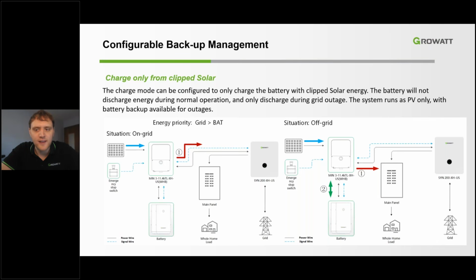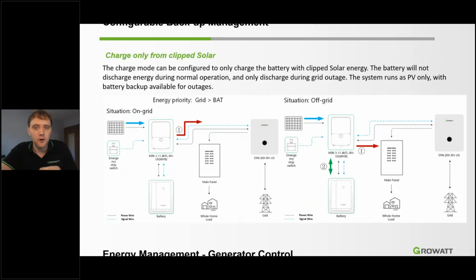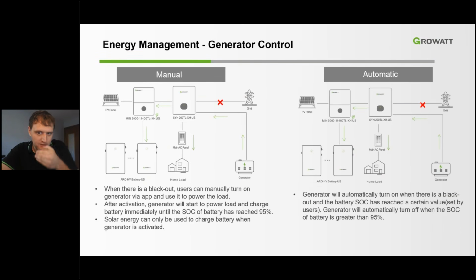These are just a few ways that the energy management system can be controlled by the inverter. And the last most important way, especially for the SYN device, will be the generator control too. So here we can see how the diesel generator or gas generator is implemented into the backup system. The system can be configured to start the generator automatically or manually through the phone application.